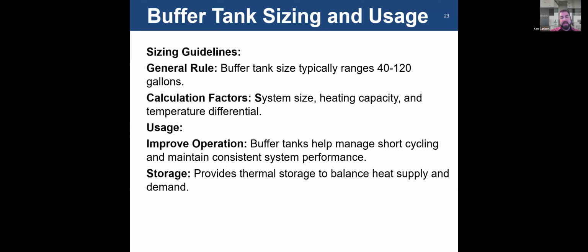We talked about before, the buffer tank is there to manage short cycling and maintain consistent performance. We talked about how the heat pumps need to go into defrost modes. They don't respond to temperature changes immediately. That buffer tank is there to mitigate some of that. So it's a requirement.